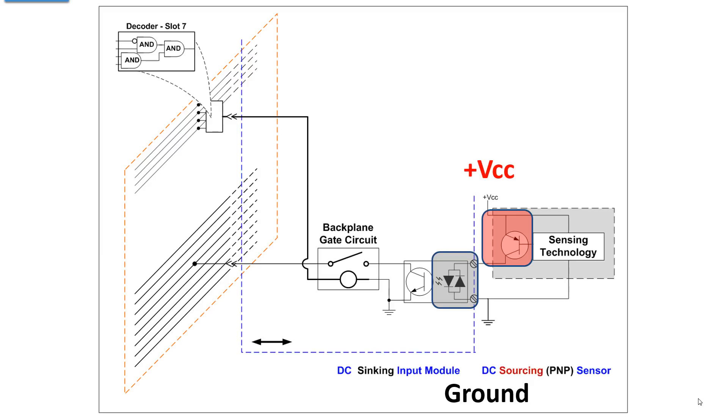Here's the fly in the ointment of this whole sourcing-sinking discussion. Every circuit has a sink and a source. When you are identifying the input module, do you identify it by where its circuit fits in the DC circuit or by what type of a sensor that you apply to it? Is it a sinking module because its input circuit sinks the sensor? Or do you call it a sourcing module because it requires a sourcing sensor?